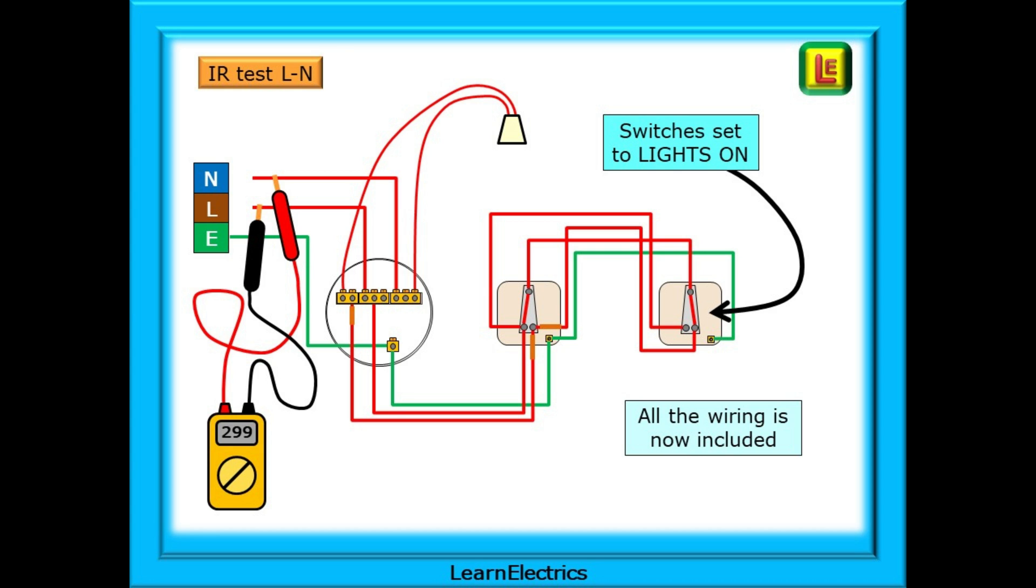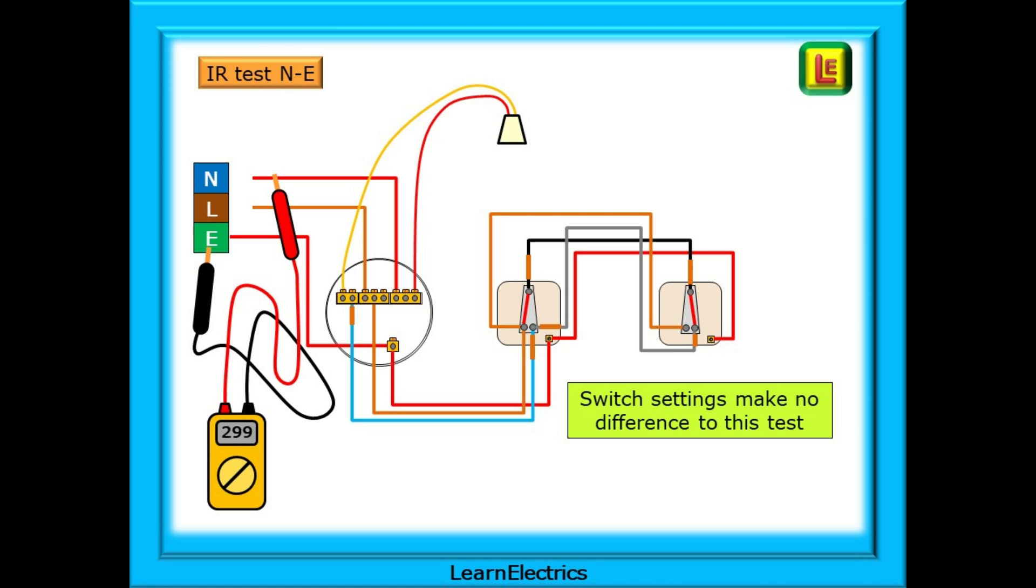Why do this? Because we don't really know if the lights are set to on or off. Can we be really certain? Well no, we can't. This way, we know that one of the tests has included all the wiring. Now we should carry out the same test between neutral and earth. But because neutral is not switched and earth is not switched, the switch settings will make no difference to the readings. So only one test is needed.